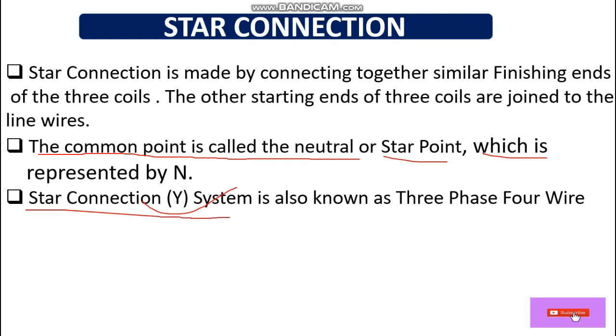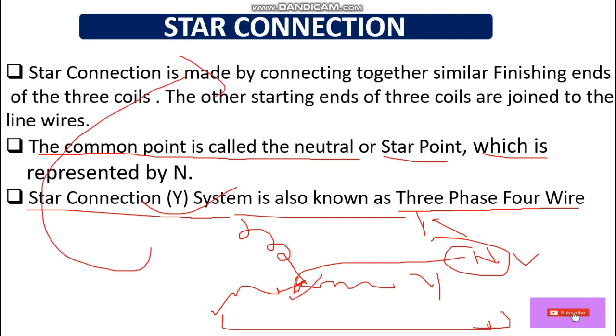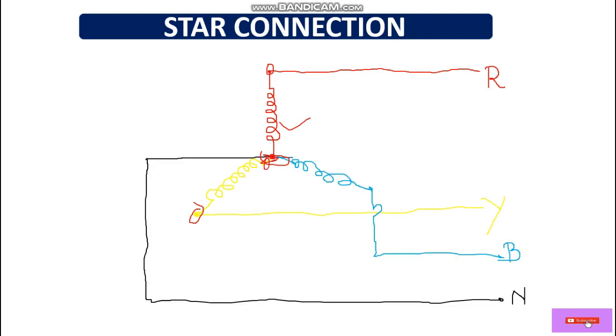Star connection is generally also called a three-phase four-wire system, as we have three phases — R, Y, B — and one additional wire which can be earth or used as neutral for the return path. Here the three coils for R, Y, and B are joined together at one neutral point, from which we can take a neutral wire wherever a four-wire system is required.